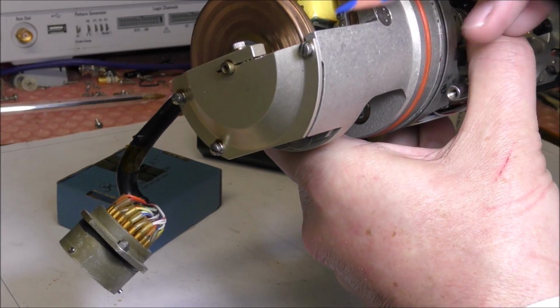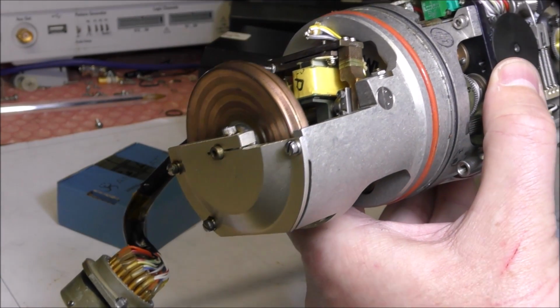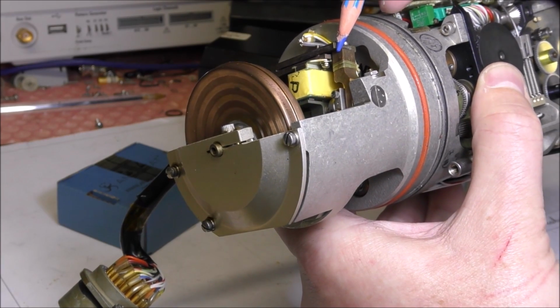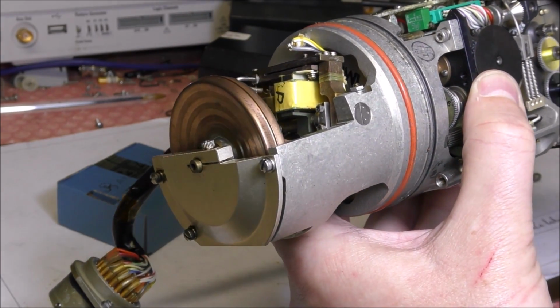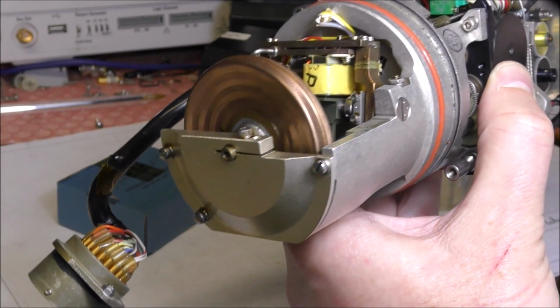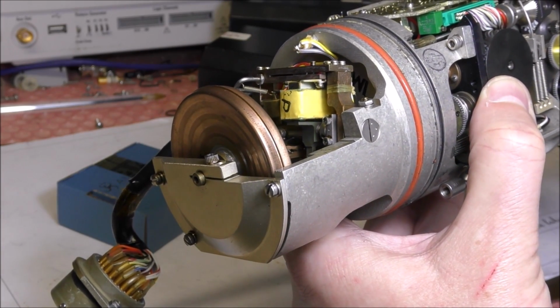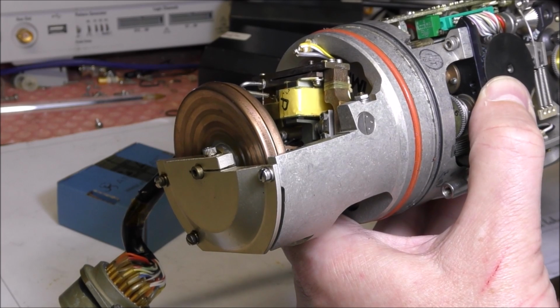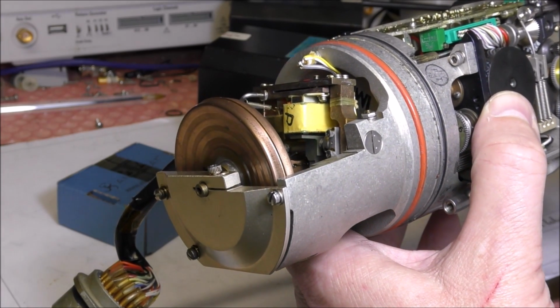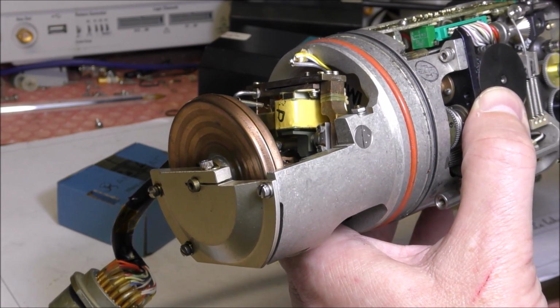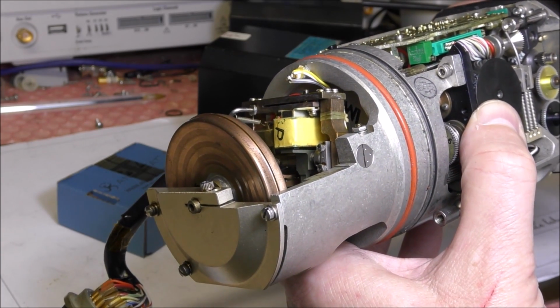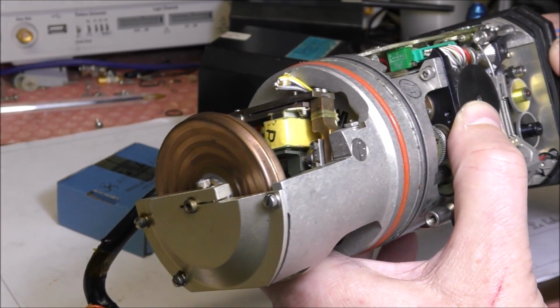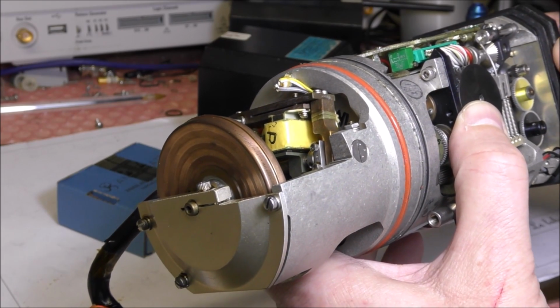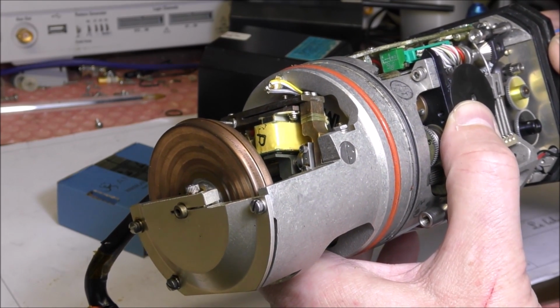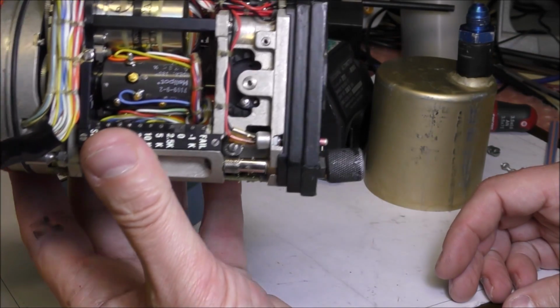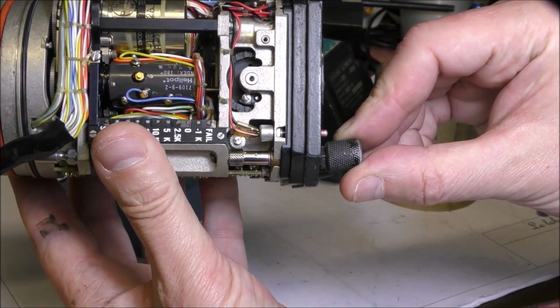So when there is a movement of the capsule, there will be also a movement of this thing in order to recover the zero position of the pick-off sensor. So the pick-off sensor has 3 coils, one excitation coil and 2 measurement coils in series and in phase opposition. So when the E bar is centered, the resulting voltage is close to 0, and this permits to the servo control loop to recover the 0 when the altitude changes. Okay, you can see also that the knob is bent here.